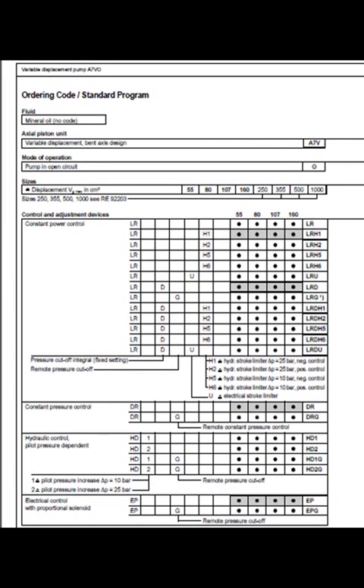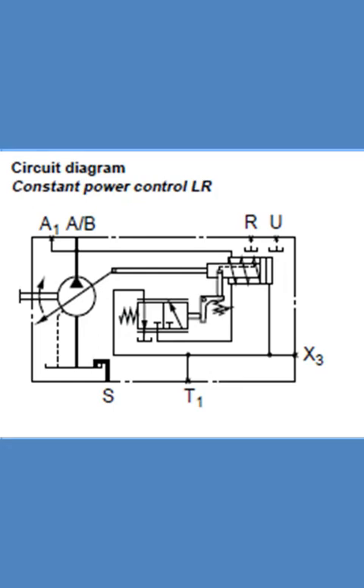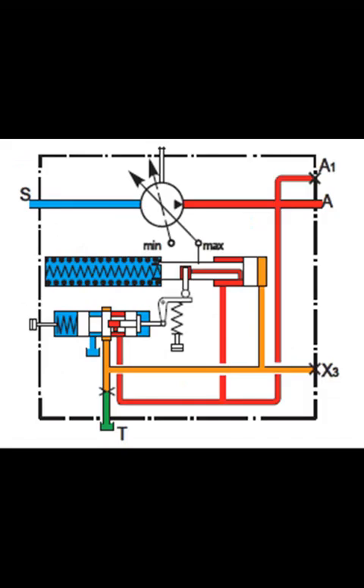Variation: Remote Pressure Cutoff G. A sequence valve with subplate takes over the function of the pressure cutoff. The valve is mounted separate from the pump and the supply piping length should not exceed 5 m. High pressure is supplied from the pump to the valve via port A1, and the valve control oil is fed back to the pump via port X3, causing the pump to swivel back towards VG min. Port E of the sequence valve and T1 pilot drain from the pump must be connected back to tank or cooler. Setting range: 50 bar to 315 bar. Any pressure relief valve included in the circuit must be set to a cracking pressure at least 20 bar above the pressure control setting. The sequence valve and subplate must be ordered separately.